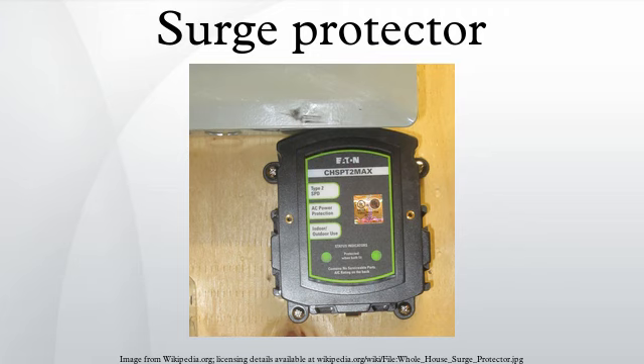These products are more expensive than simple single-outlet surge protectors, and often need professional installation on the incoming electrical power feed. However, they promise whole-house protection from surges via that path. Damage from direct lightning strikes via other paths must be controlled separately.